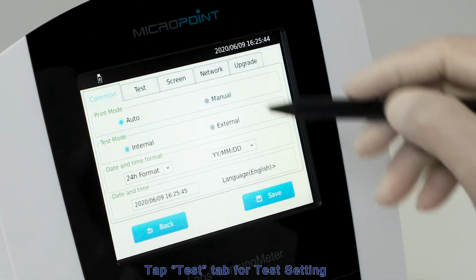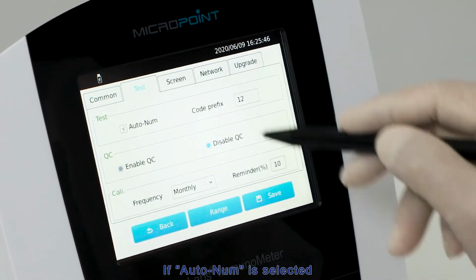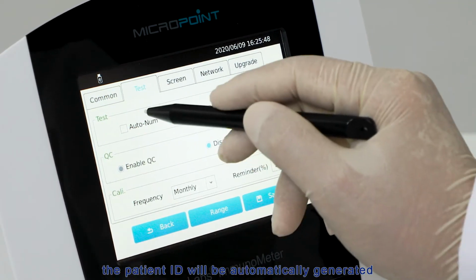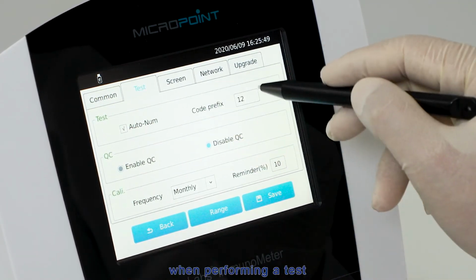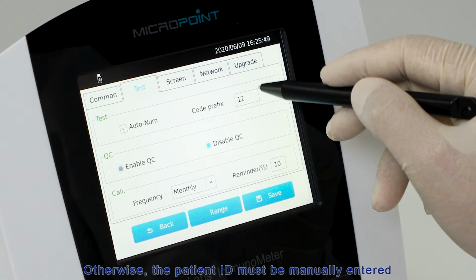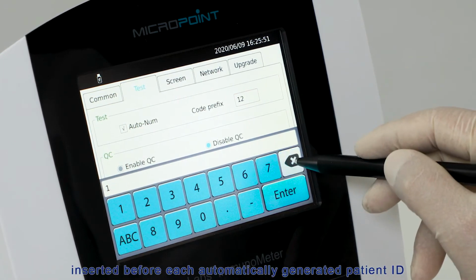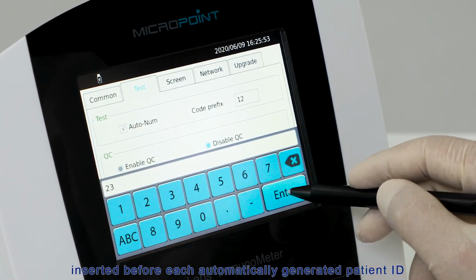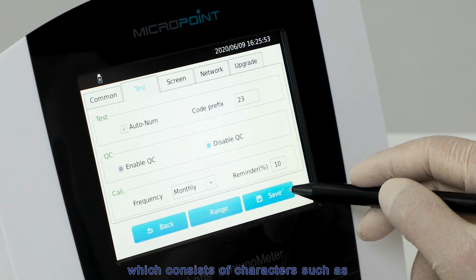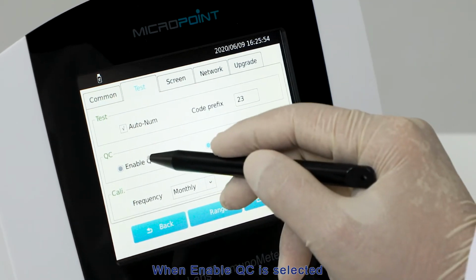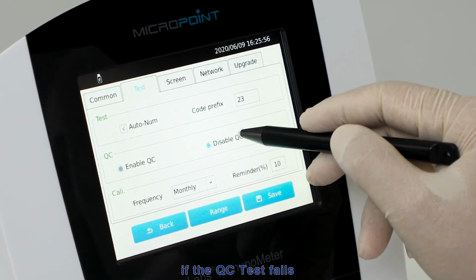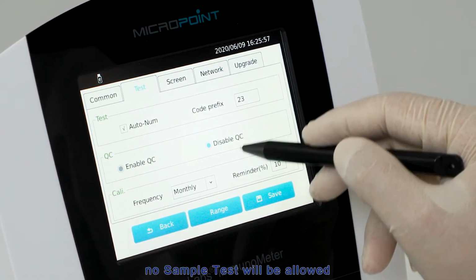Tap Test tab for test setting. If Auto Num is selected, the patient ID will be automatically generated when performing a test. Otherwise, the patient ID must be manually entered. You can set up the code prefix inserted before each automatically generated patient ID, which consists of characters such as case-sensitive alphabetical letters. When Enable QC is selected, if the QC test fails, no sample test will be allowed, while Disable QC means the QC test results will not affect the sample test.